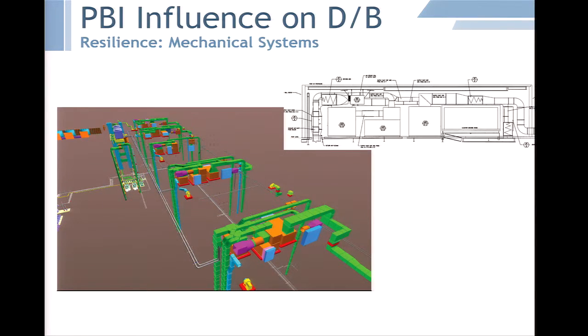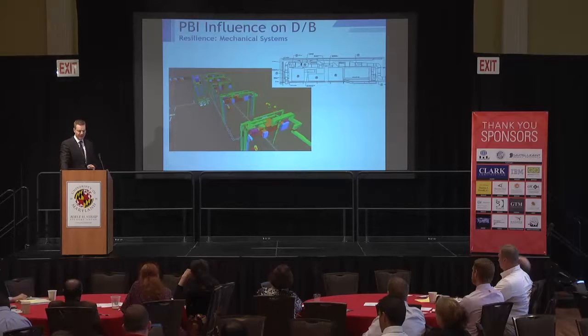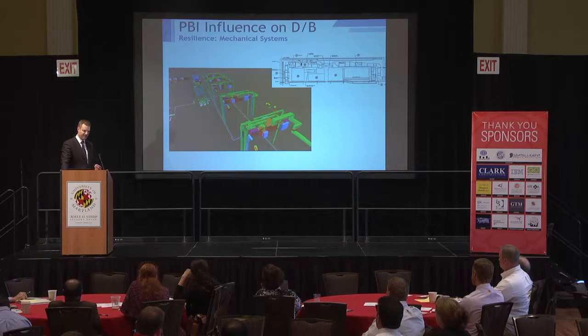What we're looking at here is an isometric cutaway of the mechanical systems for the project. Each cluster of equipment is one of the rooftop penthouses - there are 6 of those. With the penthouses, even if you had a catastrophe, they're able to operate more or less independently. So if you lose one penthouse due to some incident, you're only losing a fraction of the building. This notion of isolation means you can keep 5/6 of the building operational while repairing the catastrophe in the one, which is much better shape than if the whole building went down.